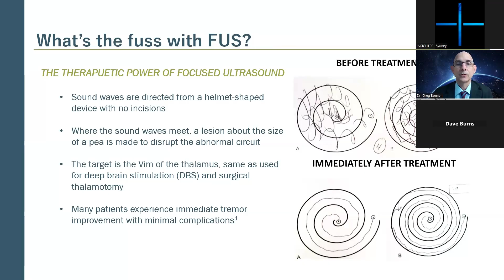And no single channel actually generates enough energy to do too much, but where they all meet in the exact same location, it deposits heat. And we're able to control the location, the amount of heat, and the duration of the heat. And that is essentially what we're doing with focused ultrasound. So it's a really elegant, very sophisticated way to do what used to be done by making an incision and drilling a hole and putting a mechanical probe that we could heat the tip of when it was in the brain and then take it out. This way, there's nothing invasive, and we can still generate a thermal ablation at the same target site.